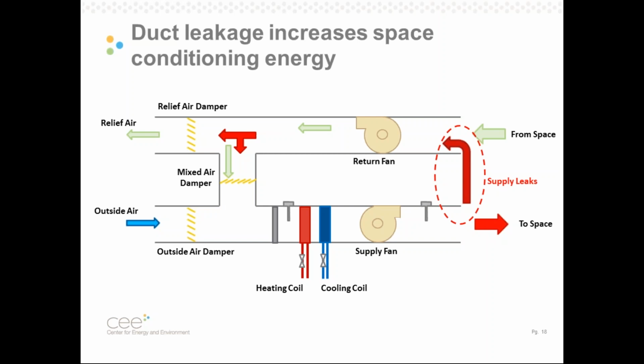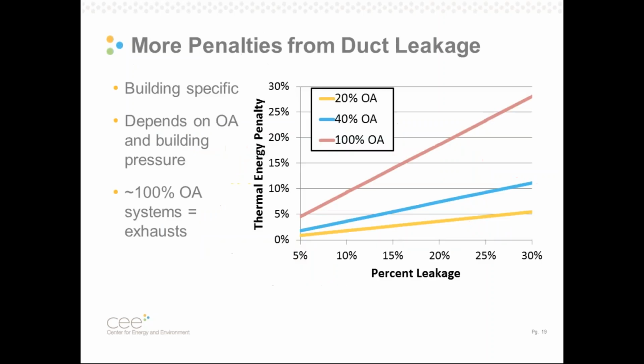This fraction of thermal energy loss depends on how much outside air we're pulling in the system. In most systems, this might be 20 or 30%. In exhaust systems or 100% outside air systems, this is a high fraction, 100%. So we got kind of hit twice in some systems. We have thermal energy penalties and fan energy penalties. It turns out the thermal energy penalties are a little bit more building and system specific. Like I said, they depend heavily on outside air. They also depend on building pressure. But we do see significant losses.